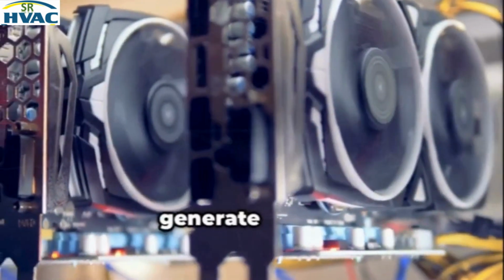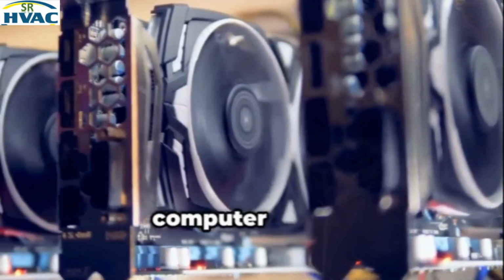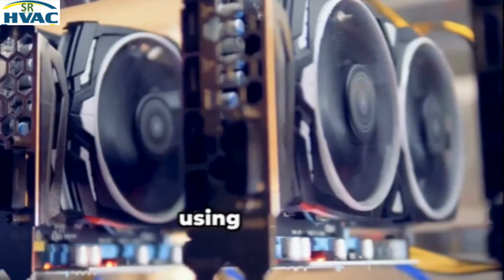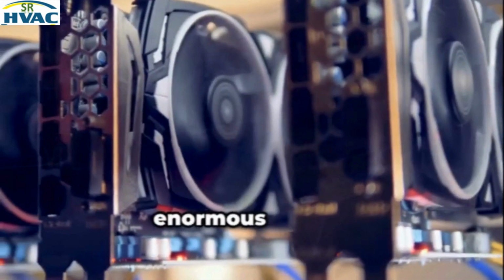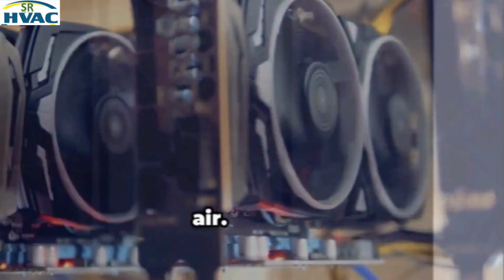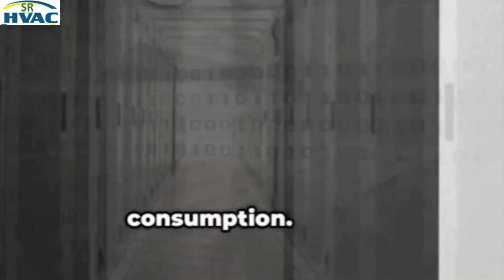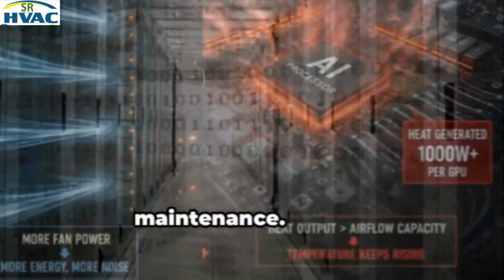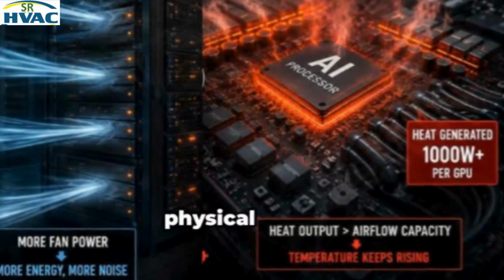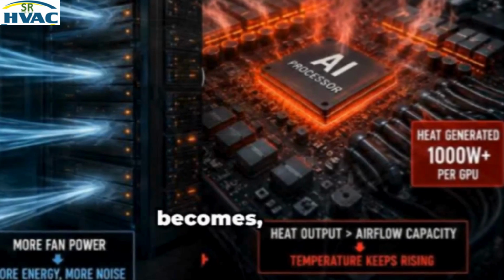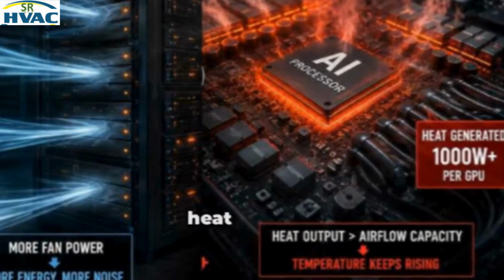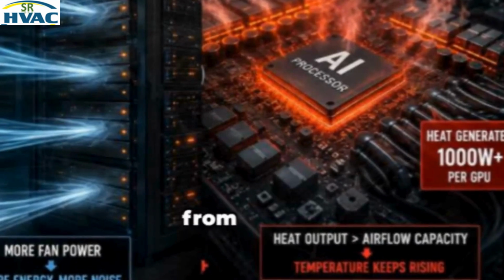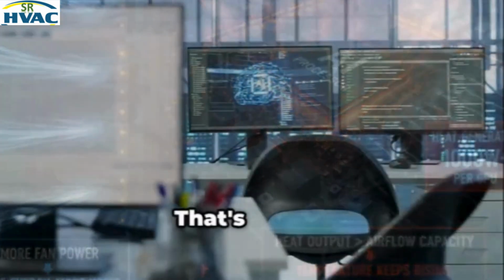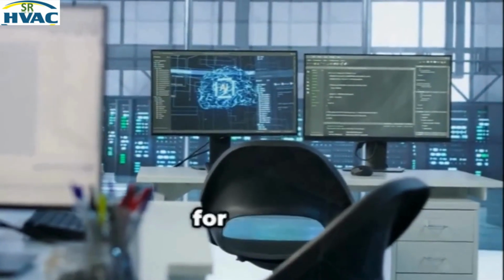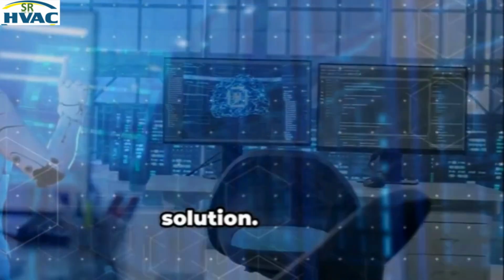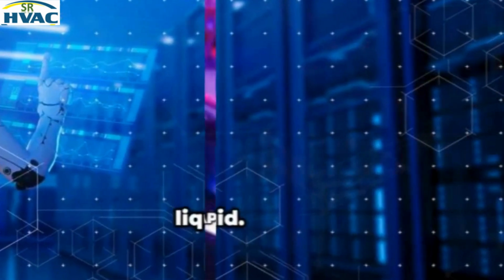Modern AI servers generate far more heat than older computer systems. To remove that heat using only air, engineers would need enormous fans moving incredible volumes of air. More fans mean higher electricity consumption, more noise, more maintenance. Eventually, air reaches its physical limit. No matter how powerful the fan becomes, it cannot remove heat fast enough from today's AI processors. That's why engineers began looking for a completely different solution, not colder air, but liquid.